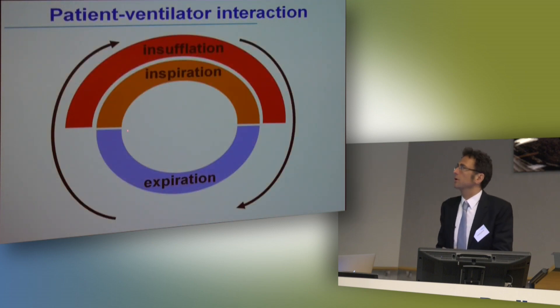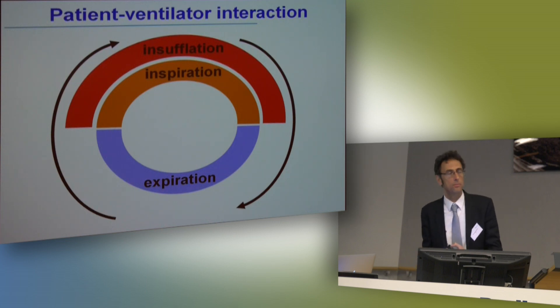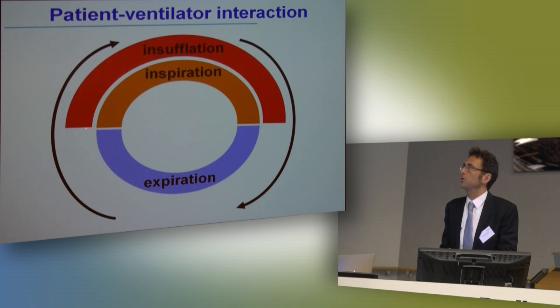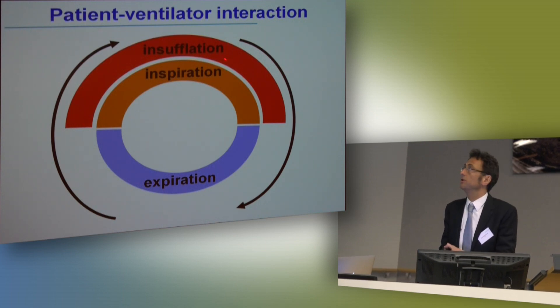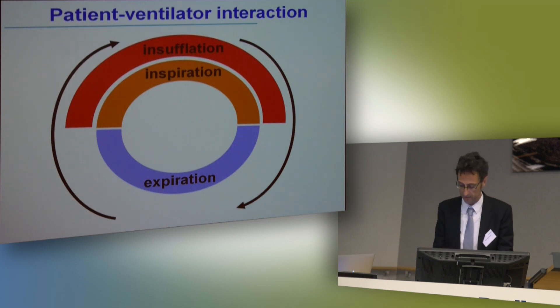Here is the patient's respiratory cycle, which is made of inspiration followed by expiration. What we expect from the ventilator is that the insufflation starts when the inspiration of the patient begins, and we also expect that the insufflation stops when the inspiration of the patient stops. That is what we try to achieve.